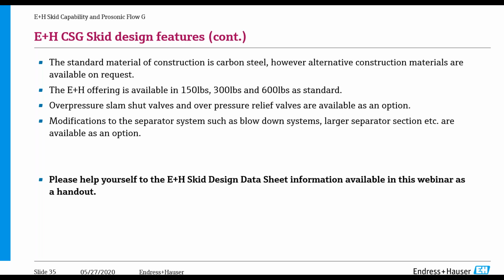Overpressure slam shut valves and overpressure relief valves are also available. Not all customers want to have that functionality on the flow metering skid itself, on the gas metering skid, but they are available as an option to be incorporated in the standard Endress+Hauser skid design as well. And modifications to the separator system, and I mentioned this earlier, such as blowdown systems, larger separator section, etc., are available as an option as well.